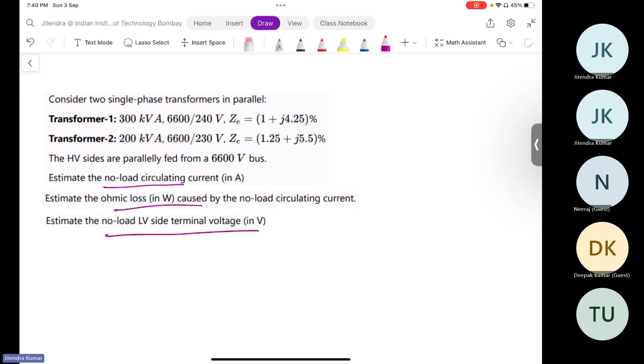Circulating current is very easy: E1 minus E2 divided by Z1 plus Z2. We have to consider that 240 volt is the rating of transformer 1 and 230 volt is the rating of transformer 2. Now Z1 is 1 plus j4.25 percent.